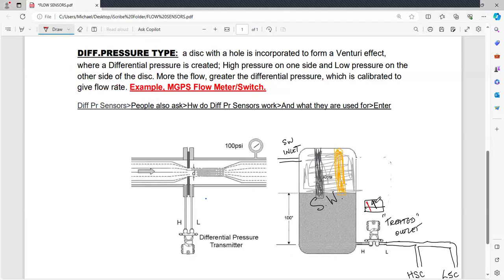So if your flow is insufficient, this black needle will come and make a physical, electrical contact with the red needle and give you the alarm to the control unit. And then that control unit sends it to the alarm monitoring system. So then when you come down, you will see that one of those things on the control unit is showing red. And then you check and you'll find that this particular flow has deteriorated. Therefore, you can adjust. Okay, the adjustment of the inlet will then therefore allow you to think.